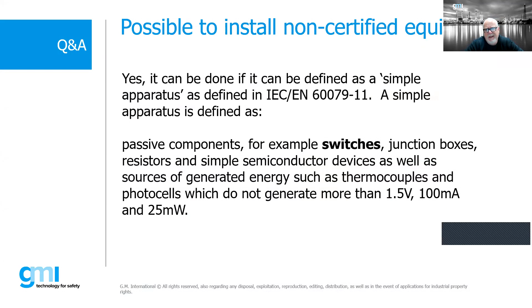Is it possible to install a non-certified simple element, like a push button, using a barrier? Yes, so a simple device. Basically, when we use barriers, anything downstream from the barrier, if it's not an energy storing device, we can certainly use general purpose equipment. That's one of the big advantages of going with intrinsic safety. We don't necessarily have to have all very expensive equipment. So yes, we can use things like switches, resistors, simple semiconductor devices.